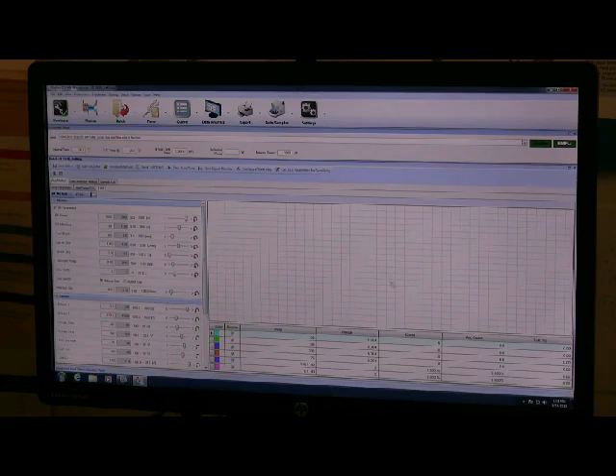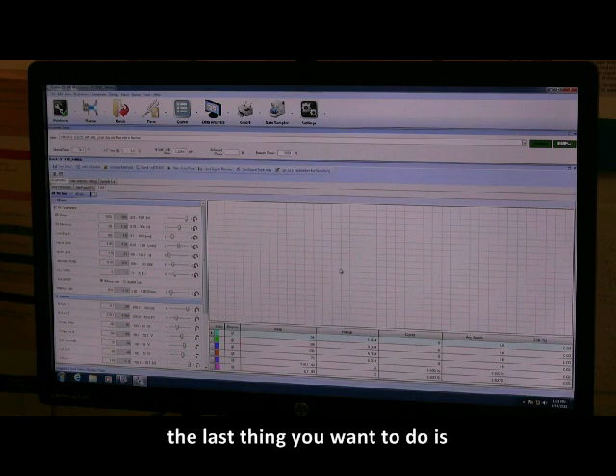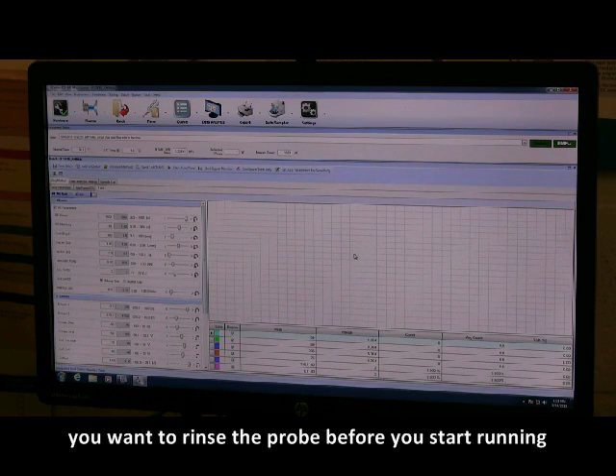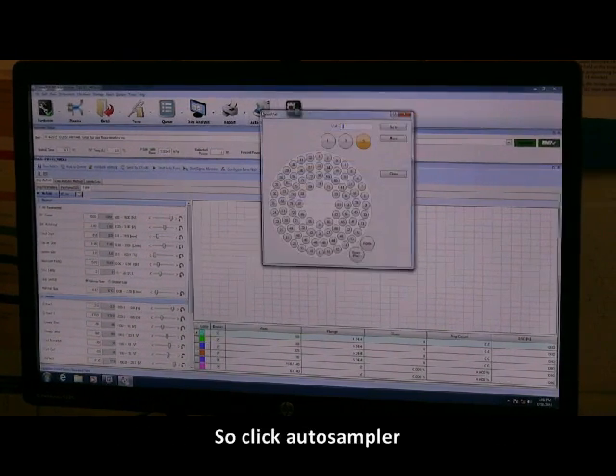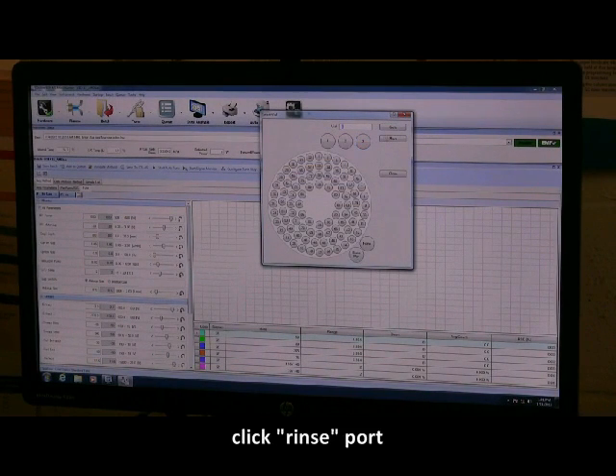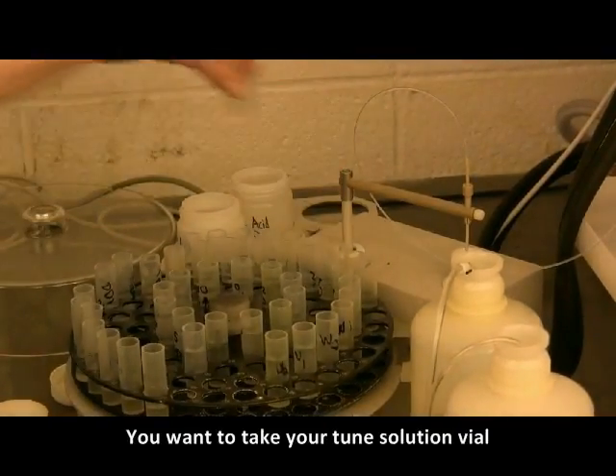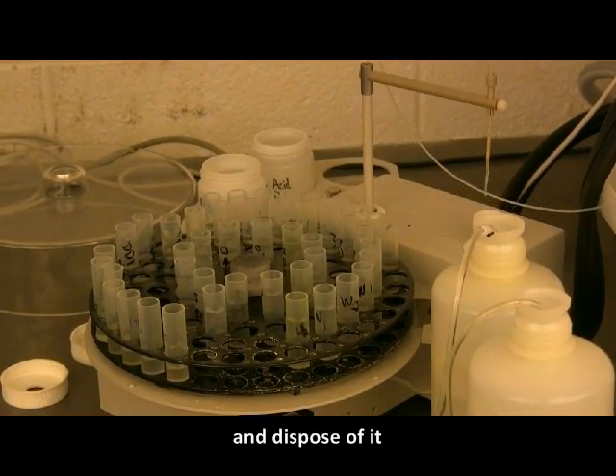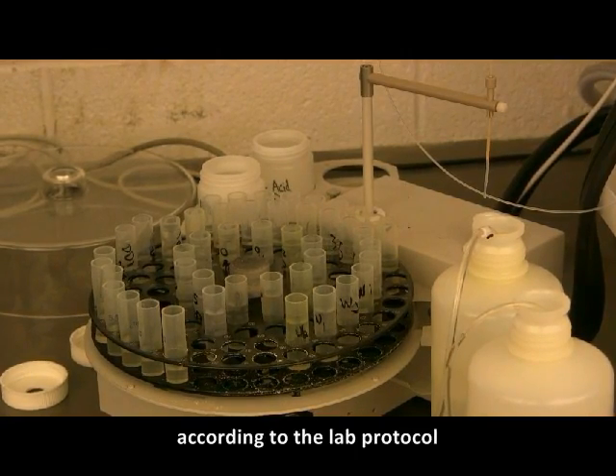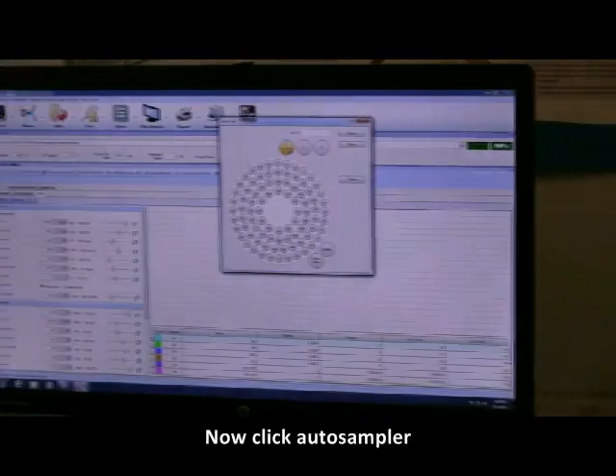So now what we're going to do is click Save Batch. So now that you've tuned, the last thing you want to do is rinse the probe before you start running. So click Auto Sampler, click Rinse Port, Go To. You want to take your tuned solution vial and dispose of it according to the lab protocol. Now click Auto Sampler and you want to go to Vial 1 and click Go To.